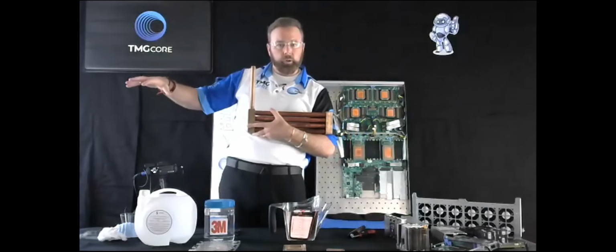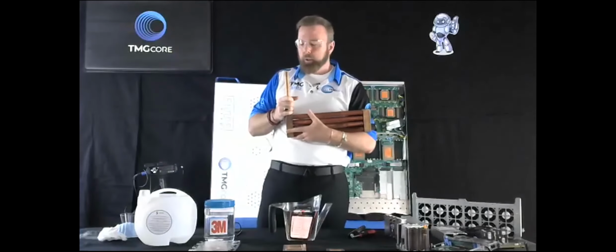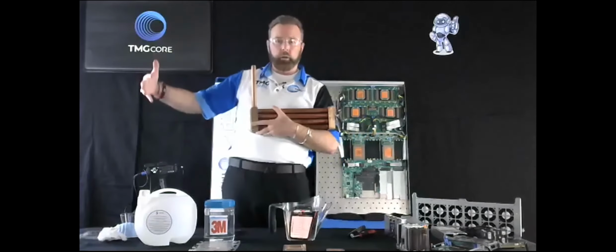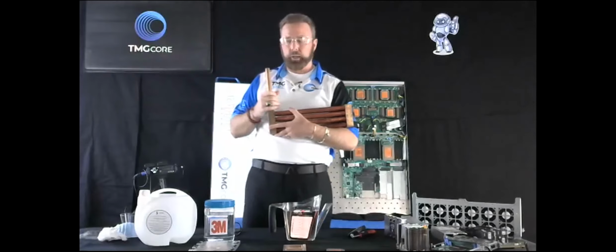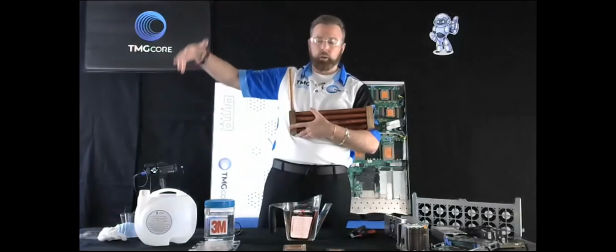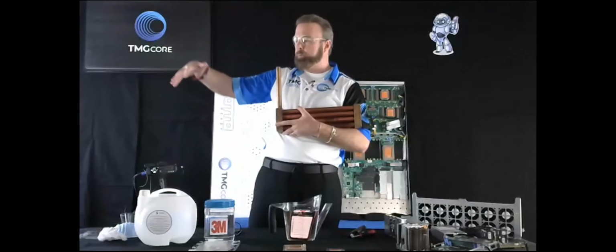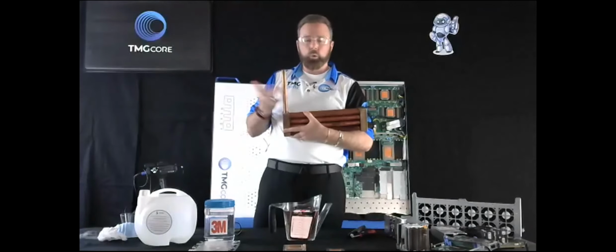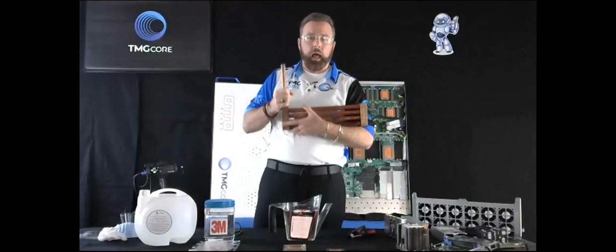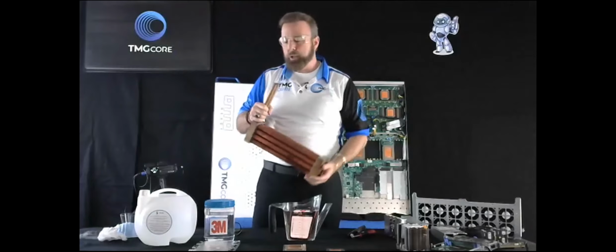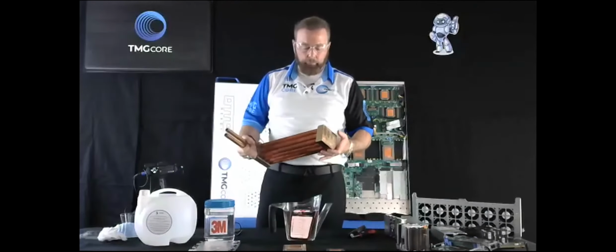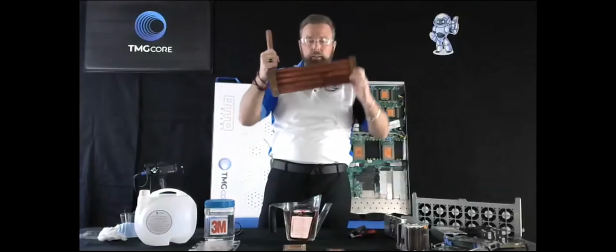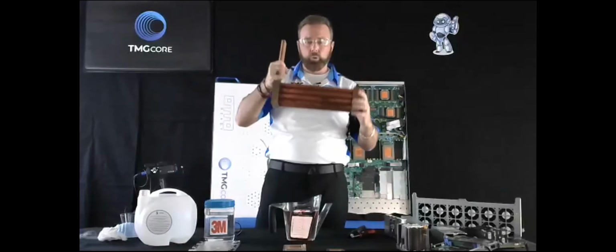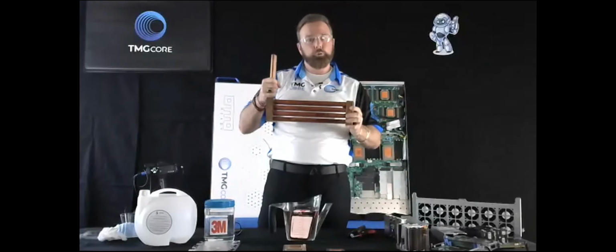Or you could use a dry cooler, which doesn't use water at all, and that's your secondary, basically final heat rejection. Or a cooling tower, a very high efficiency closed loop cooling tower or something like that. It just depends on how big the unit is, how big the final heat rejection needs to be. But these are the cooling coils that go inside, that collapse the vapor and turn it back into a liquid, as part of the two-phase process.